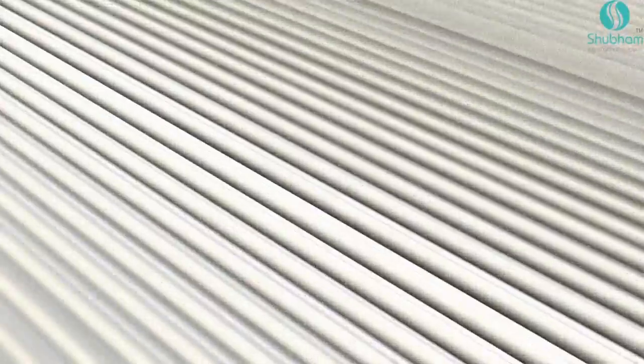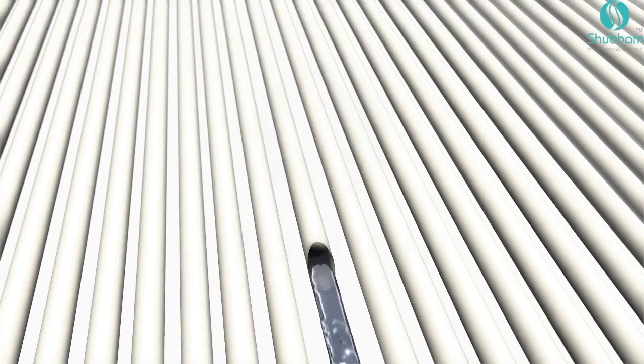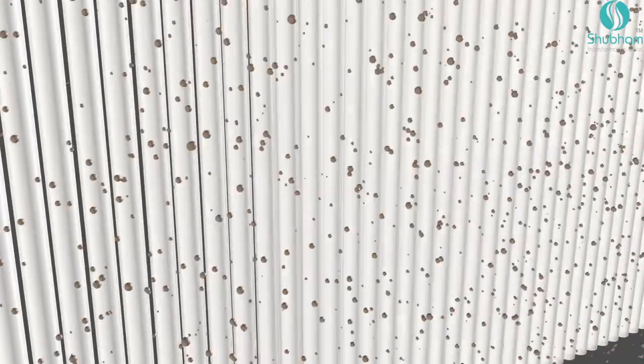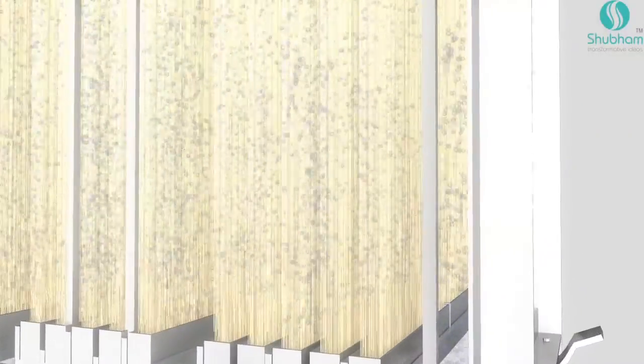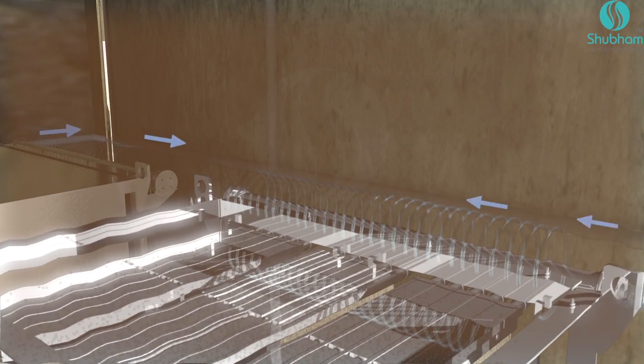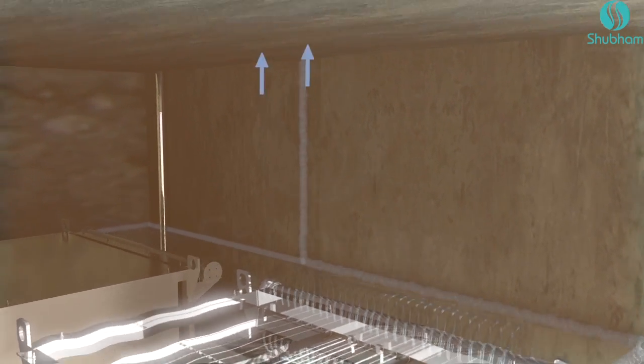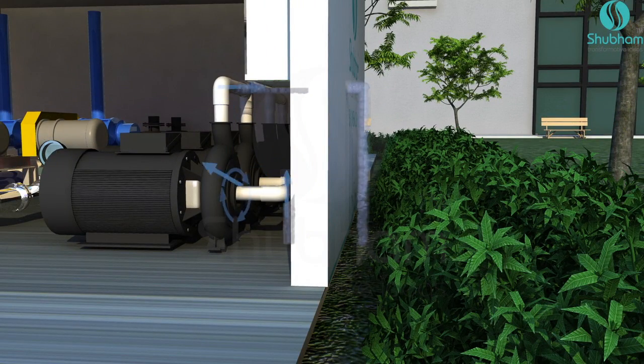The membranes are made of millions of ultra fine fibers. These fibers allow clear water to pass through while restricting pollutants outside. Each module has its own continuous and automatic cleaning system where air keeps scouring the membranes throughout the process. Clear water is then transported from the membranes through capillaries to a common header connected with suction pumps.